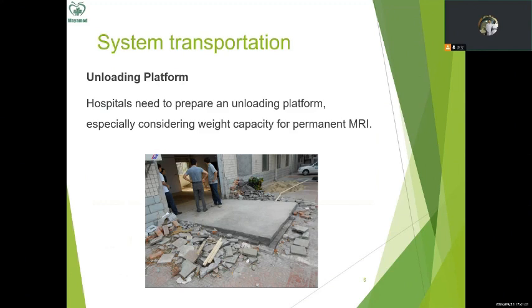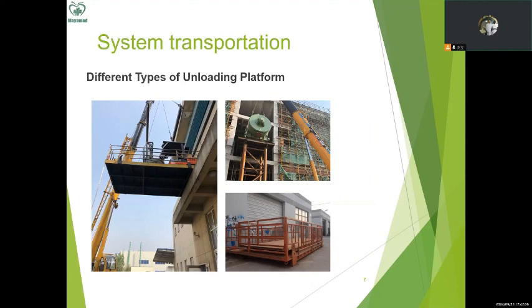And after the system has been transported near the department, the hospital also needs to use a prepared unloading platform as in the image below. Especially we need to consider the weight capacity for permanent MRI, and then we can release the MRI from the truck to this unloading platform. And there are different types of unloading platform, like in the pictures below. They are the moving unloading platform, or the unloading platform can even be on the second floor or third floor. Because, as we know, the 1.5 Tesla or CT scanner, if necessary, we can install on the second or third or even higher floors. So in this case, we use the unloading platform in the pictures and move the system into the hospital department.